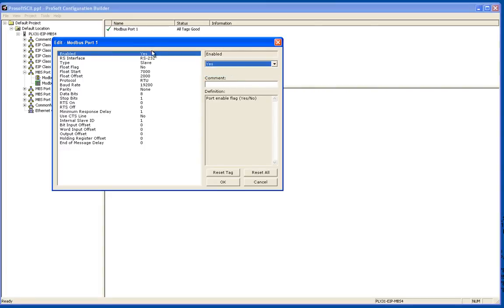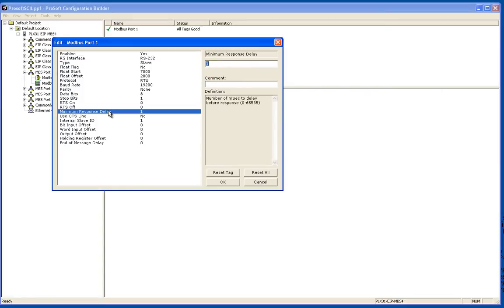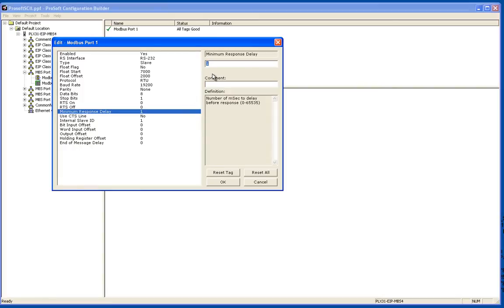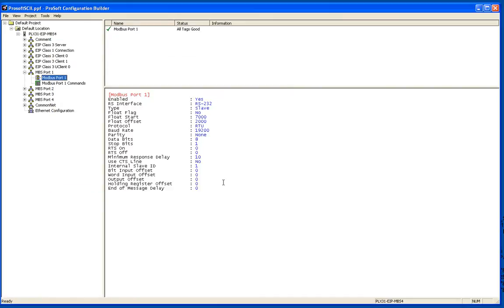Now I'm going to change the minimum response time. This is how long the Modbus port waits before it responds to a master command. I'm going to increase this to a 10 millisecond response time. Essentially the Modbus master is going to issue a request and 10 milliseconds later the Modbus slave port is going to respond. That's about it for the Modbus port configuration.